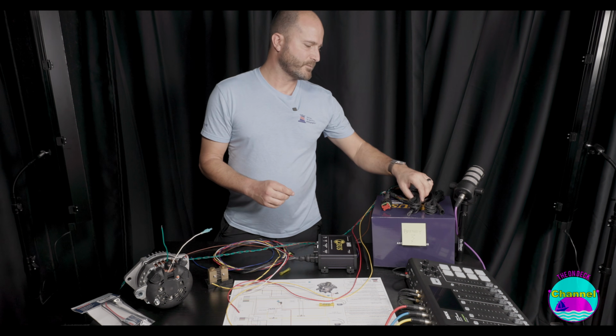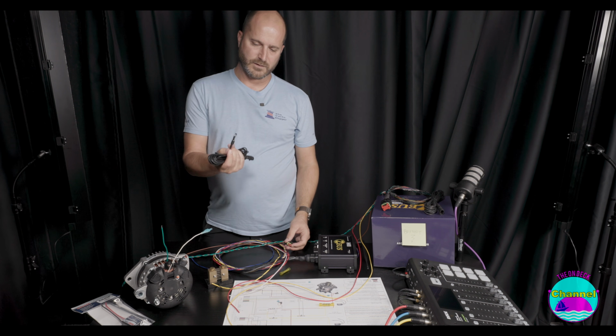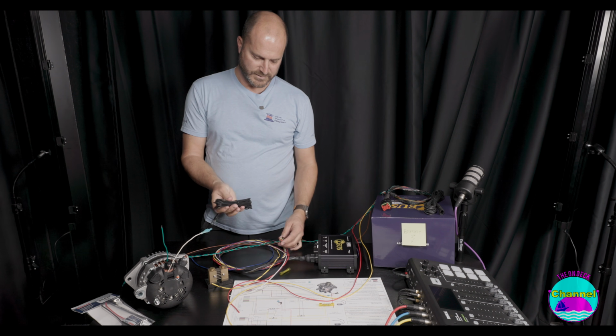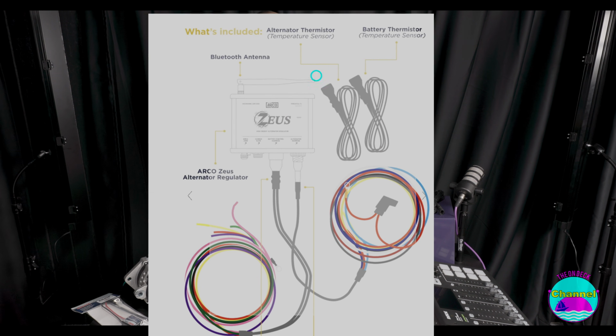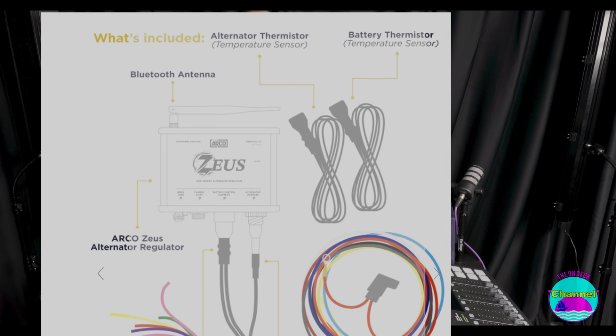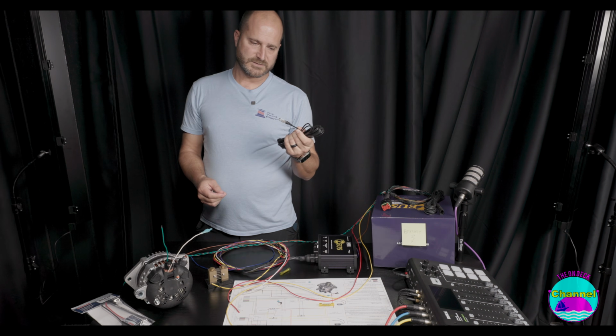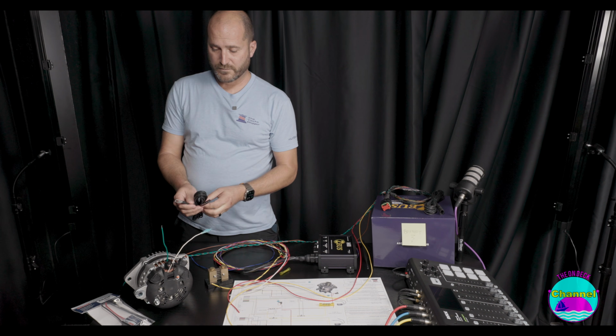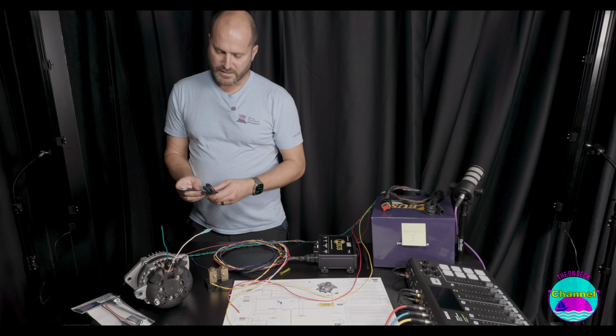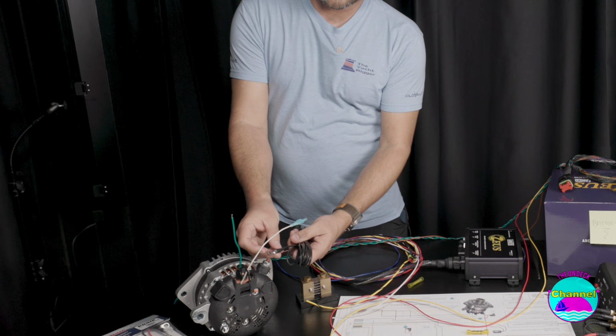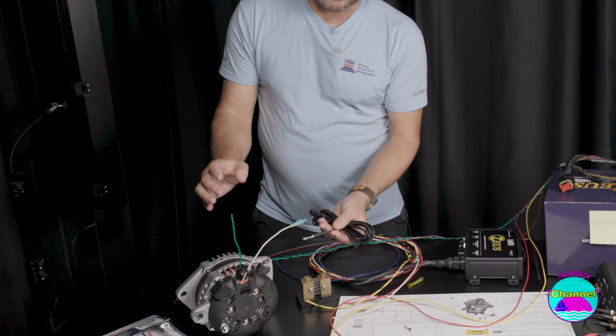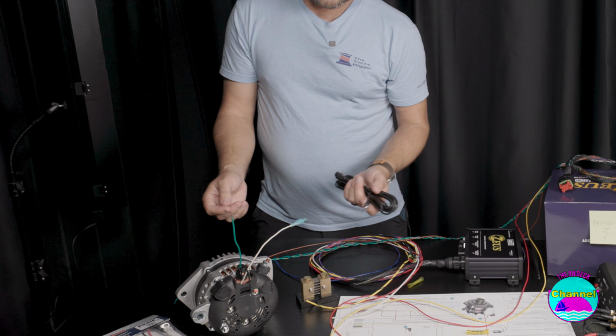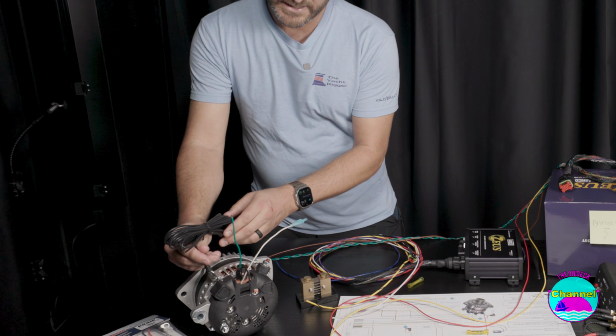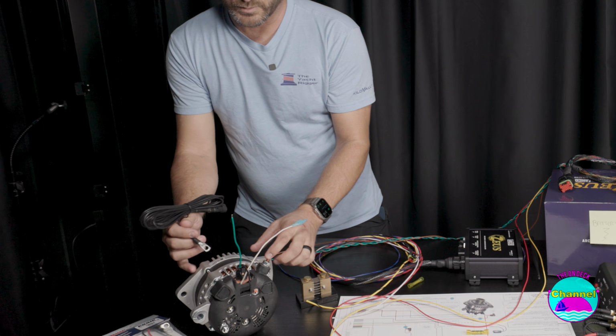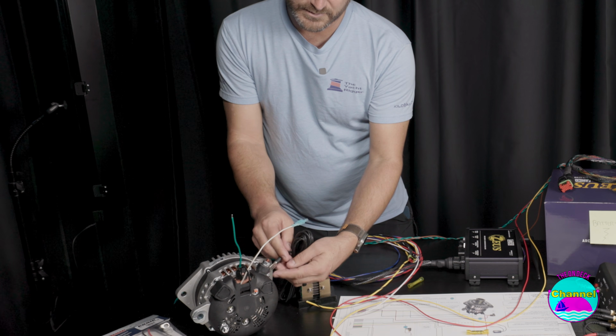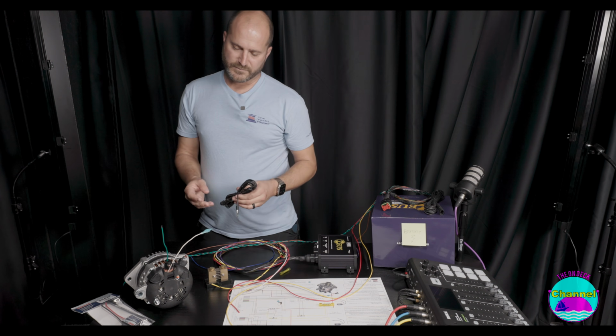One of the most important parts, the last wire here, is the thermistor for the alternator. It's just a quick connect, and the wire's a little long—you can coil it, zip tie it, and put it away. This is one of the most crucial pieces for preventing the alternator from overheating. Some people put it on the negative lug on the case. Ideally it would be right on the core, but that's often not possible. If you can put it on the case at the back, sometimes you can undo the bolts holding the case together, put them back, and mount the thermistor there. That's a good spot for it.